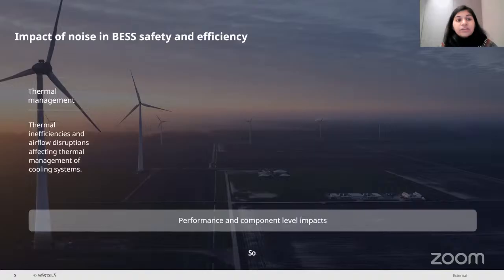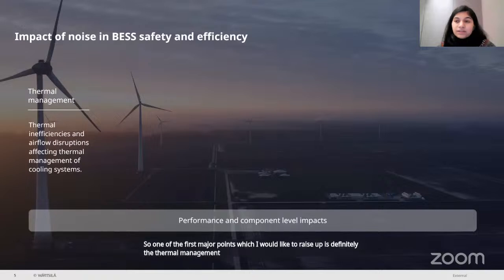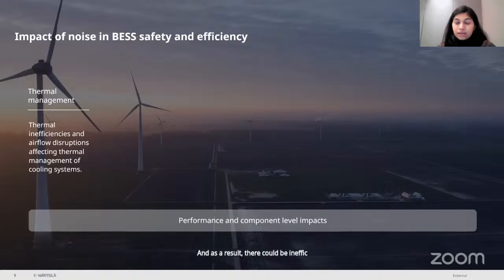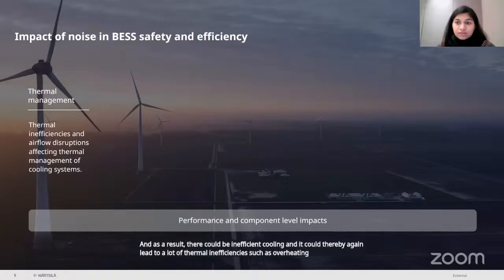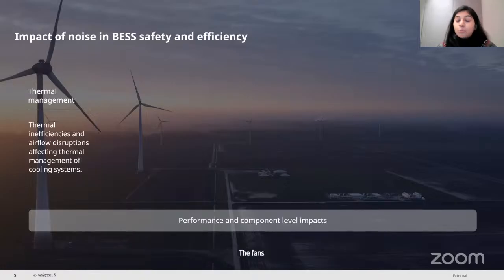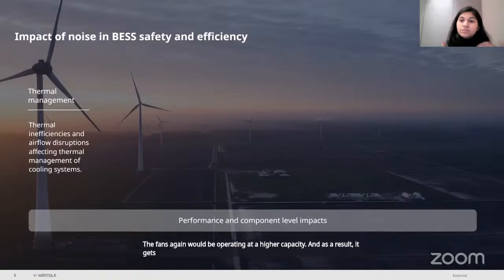One of the first and major points I would like to raise is definitely thermal management, because excessive noise is often an indication of issues with the cooling systems, such as the fans or the HVAC units. In many cases, if they're not designed properly or not mounted properly, it could lead to airflow disruptions and a lot of turbulence. As a result, there could be inefficient cooling, which could lead to thermal inefficiencies such as overheating and thermal runaway.